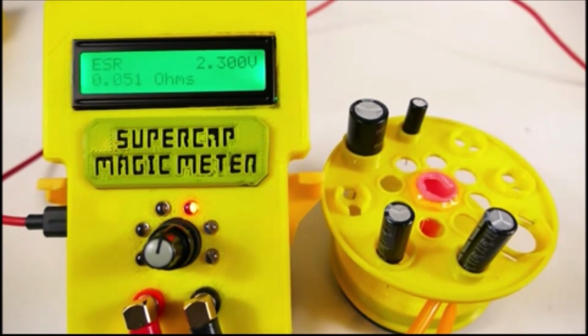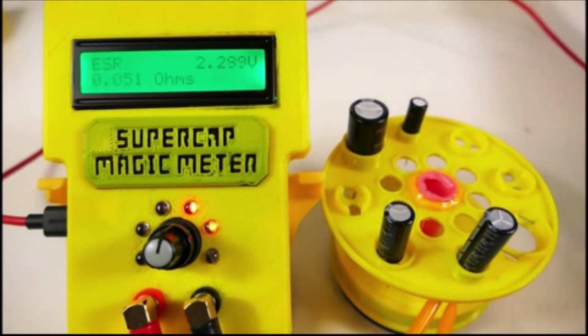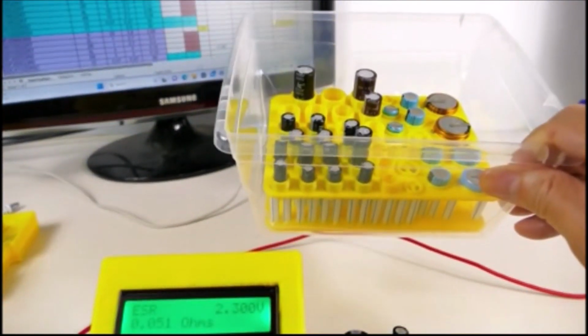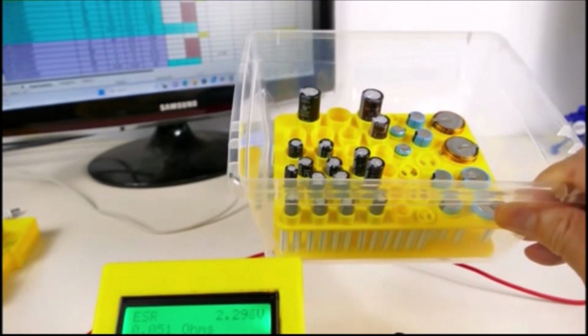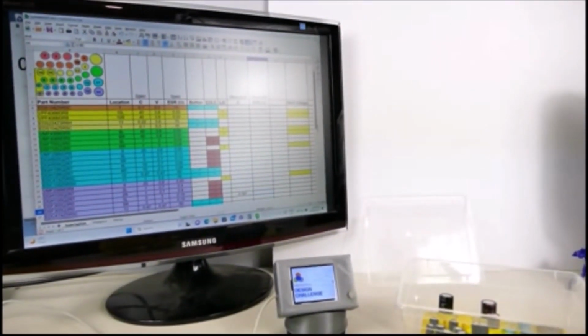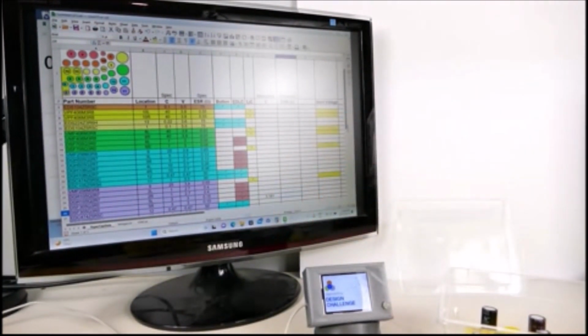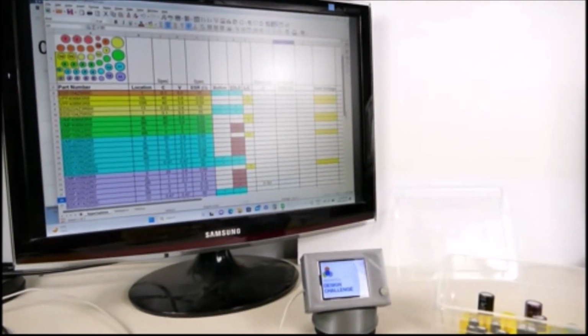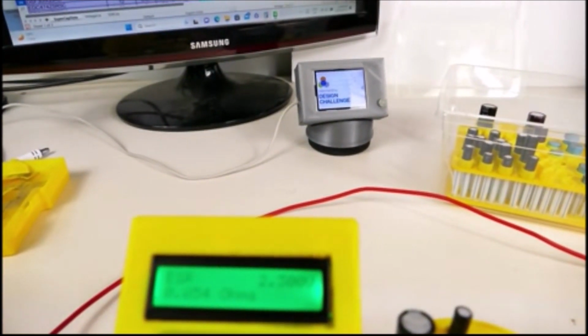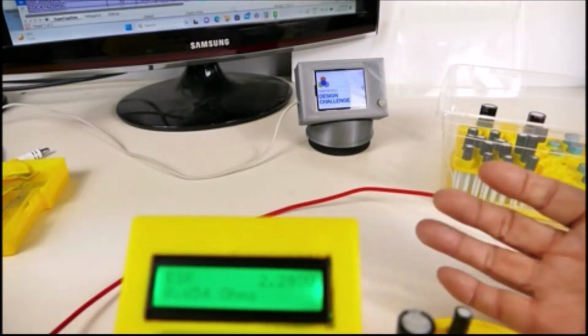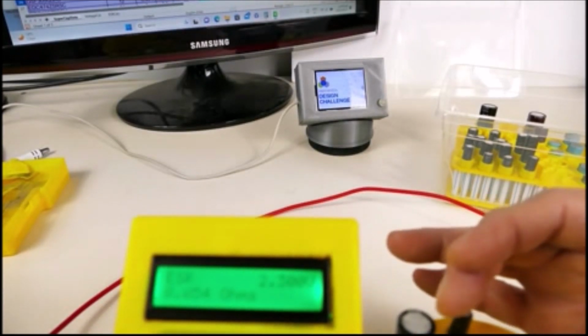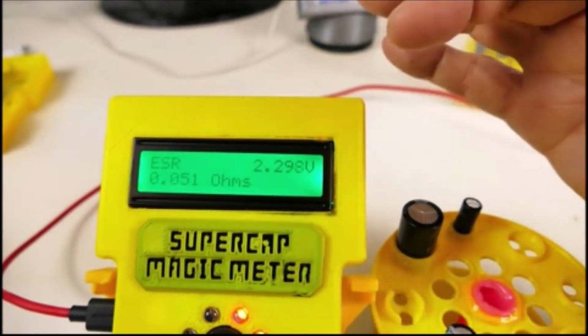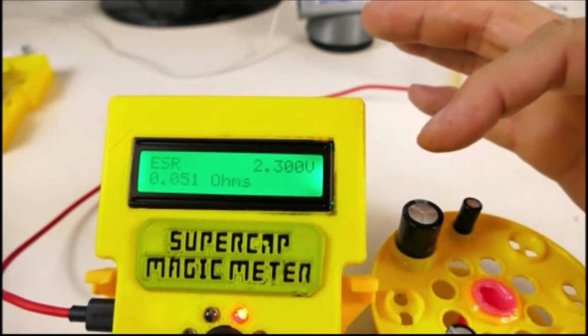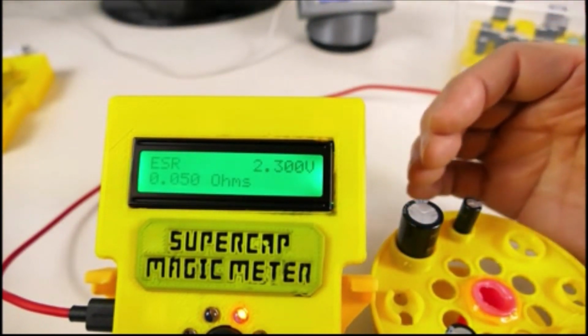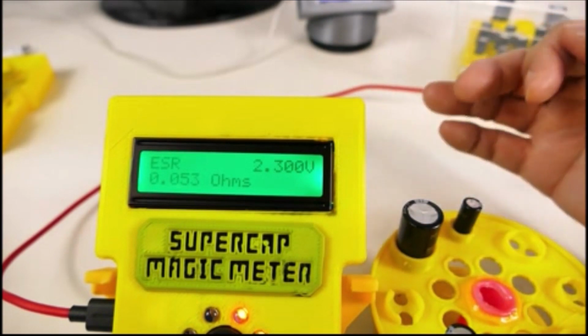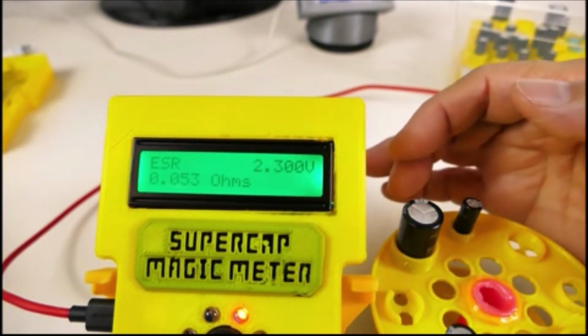Okay, so what I'm going to do is just run through the whole chassis full of capacitors here and take some readings and populate the spreadsheet with all the values I get, just to show that I'm taking some readings. But in fact, we're not trying to prove the actual value of the capacitance, because I don't have any way of confirming what the reading is on the meter. I can get readings which seem accurate enough, but they are not calibrated to any meter giving me a precise number. So I'm just doing it by calculation.